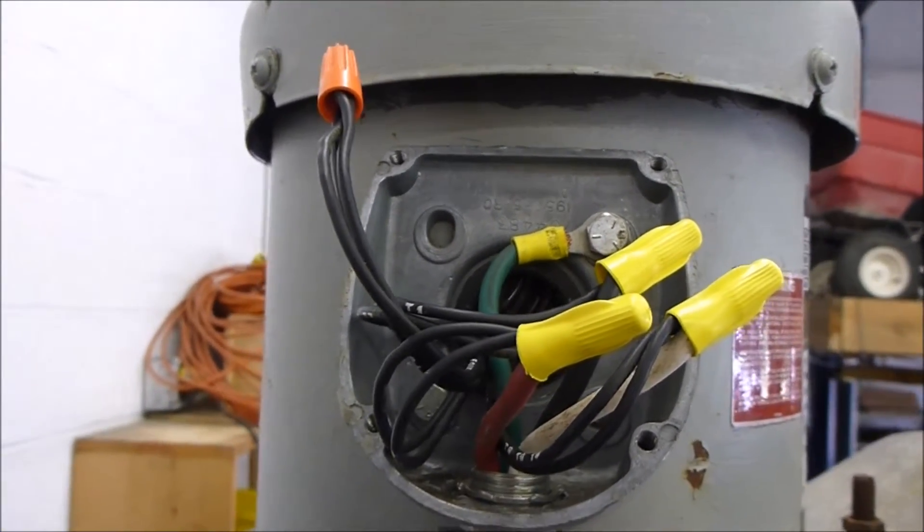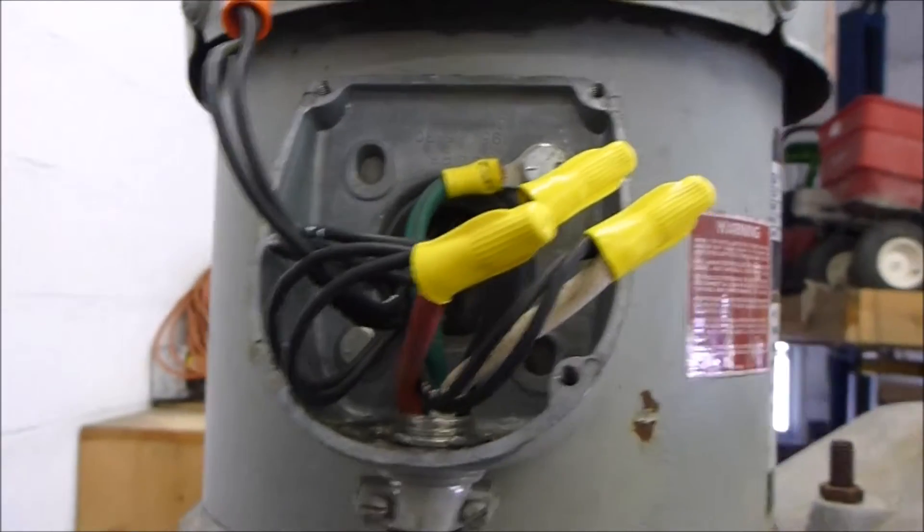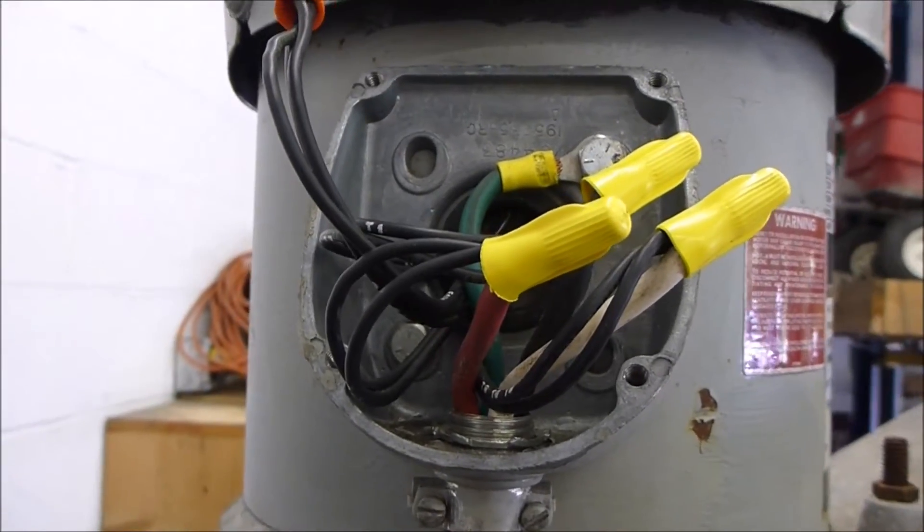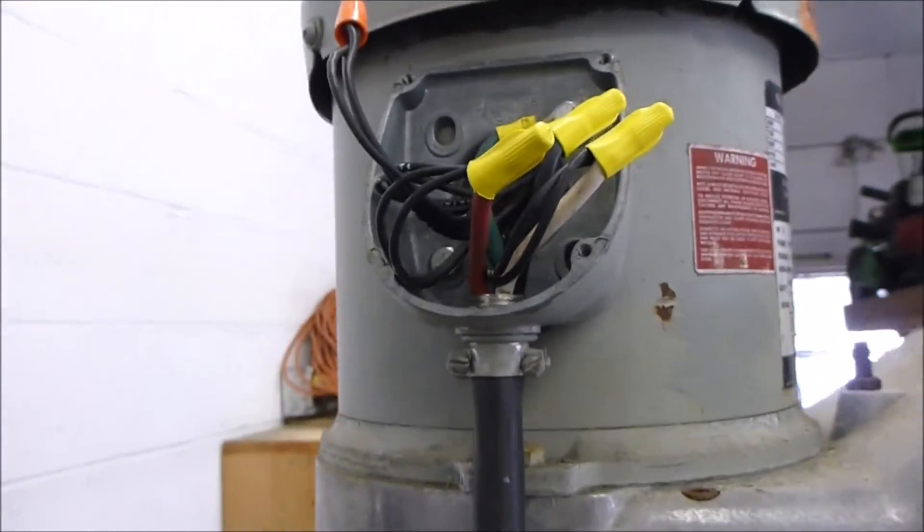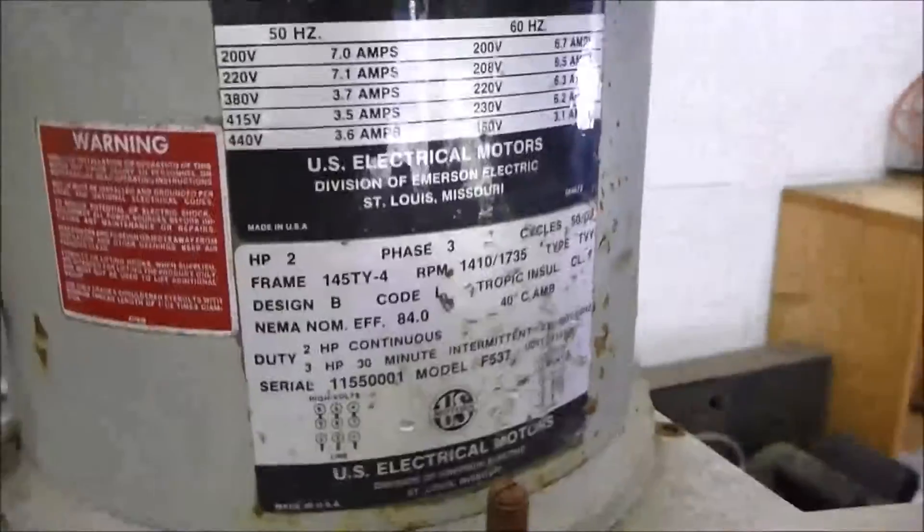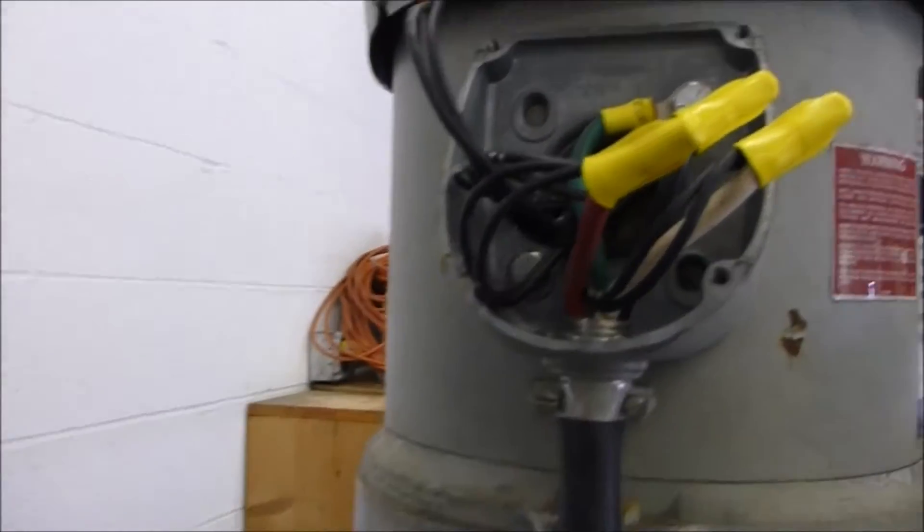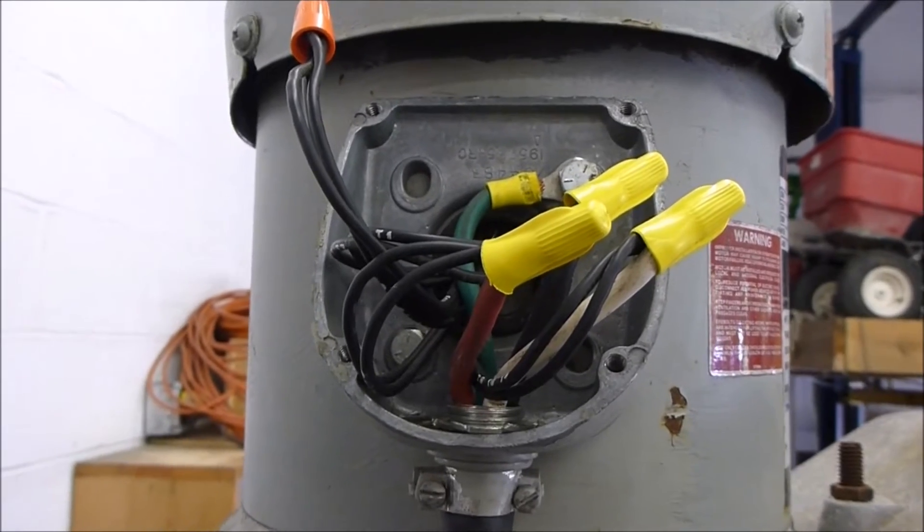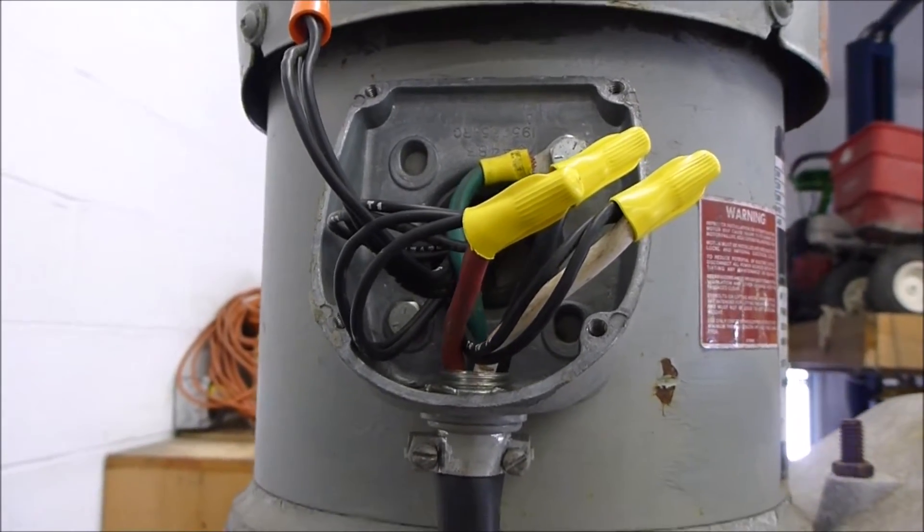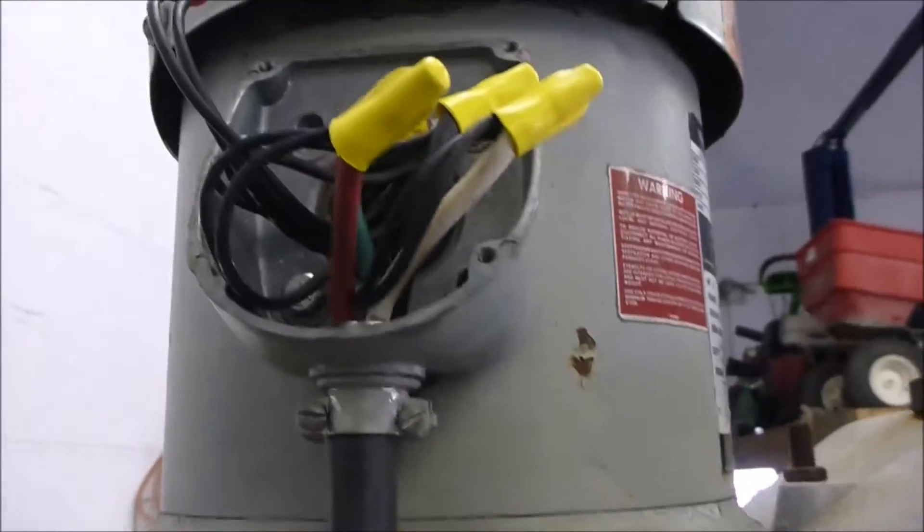I've removed the switches and other things in between the plug and the motor. On the motor, I went ahead and connected it in the low setting. That connects the four, five, and six wires together, the one and seven to the black, the two and eight to the white, and the three and nine to the red.